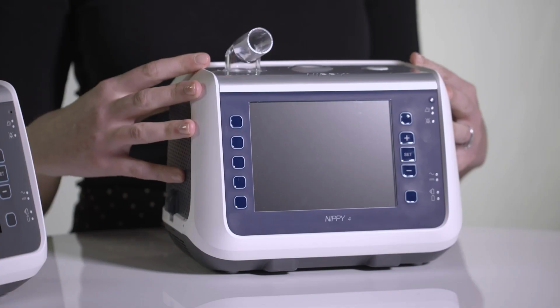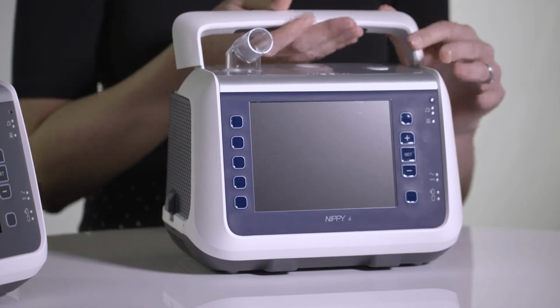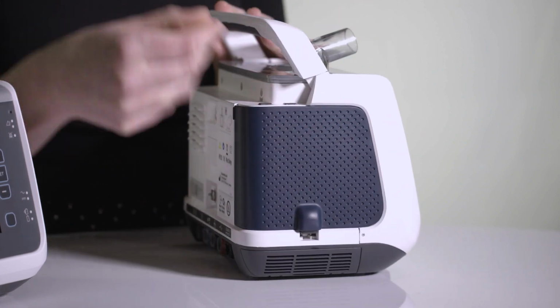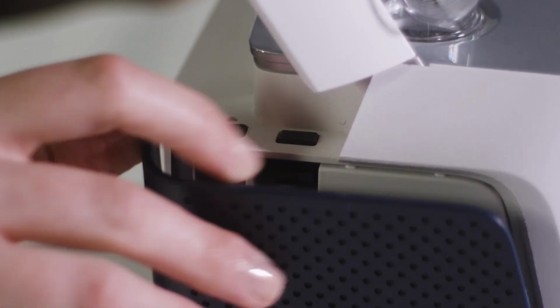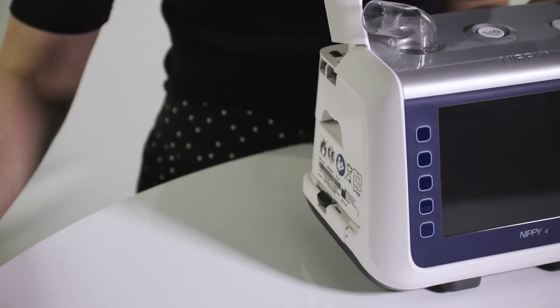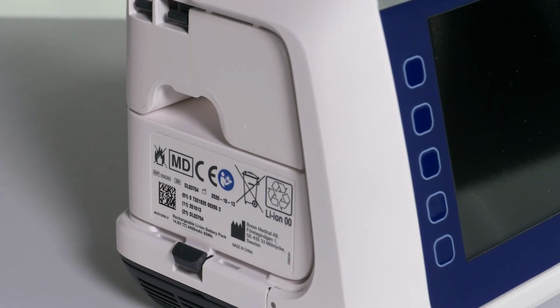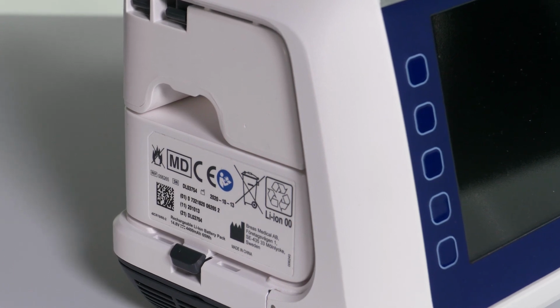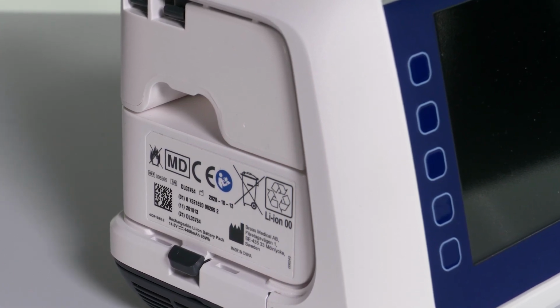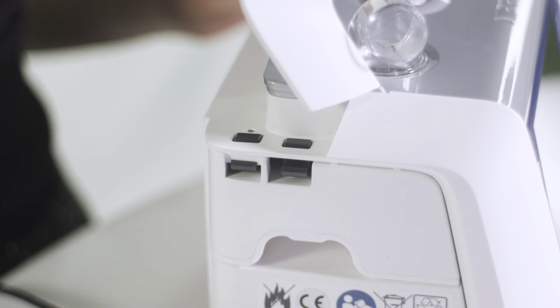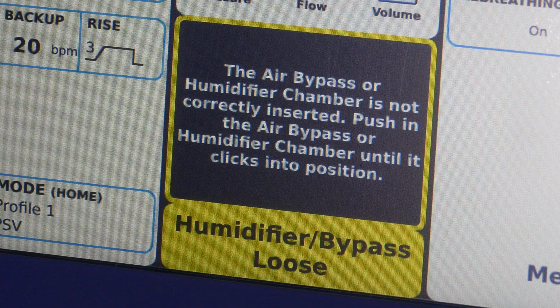To insert the click-in battery, when looking at the device from the rear, lift the carry handle and on the right-hand side press the innermost button closest to the handle, button labelled number 1, to release the side panel. The battery fits below the air bypass chamber. Make sure both are clicked into place fully before replacing the side panel. If they are not clicked in fully, an alarm message will appear on the screen.